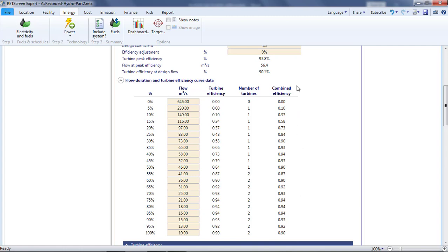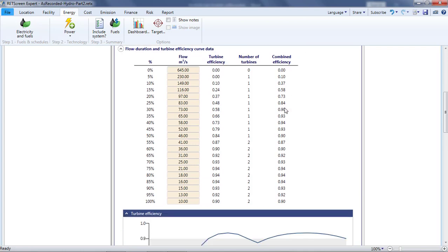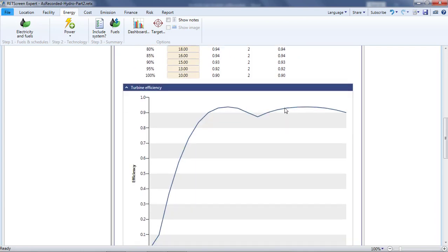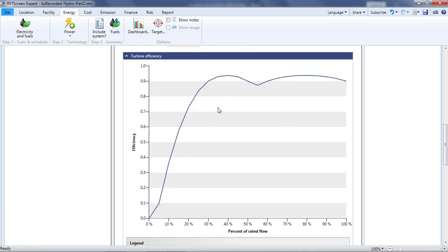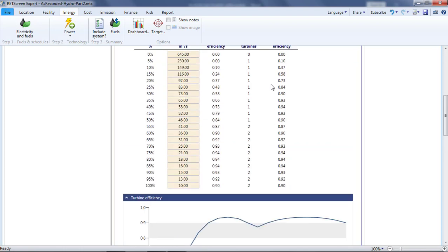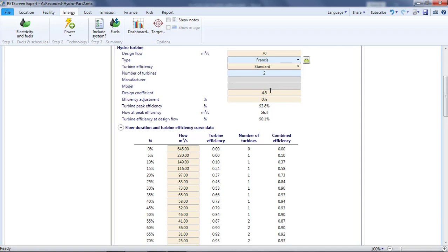Now let's look at the turbine efficiency that RETScreen has proposed. I can see this in the graphic below the table where the double hump reflects the peak efficiency with either one or two turbines. I can get key information from the results that appear below the hydro turbine input parameters. The peak efficiency is just under 94%. This occurs at around 80% of rated flow for a single turbine. For the project as a whole, this occurs at 56.4 cubic meters per second. At flows above this, the efficiency declines, reaching 90.1% at full flow.